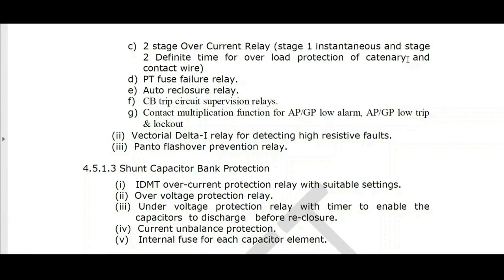The difference between definite time and inverse definite time is that definite time is only based on a current crossing a specific threshold. For example, 2 amps, let us say. The moment current crosses 2 amps, the relay will start a timer. At the end of the timer, it will trip. This timer is going to be fixed. It can be, let us say, 5 seconds. Whenever the current crosses 2 amps, in 5 seconds, the relay will trip. This is called definite time.